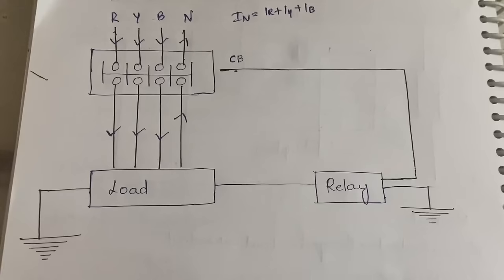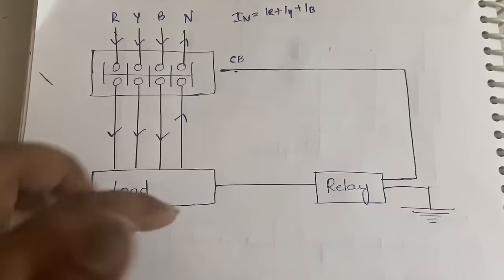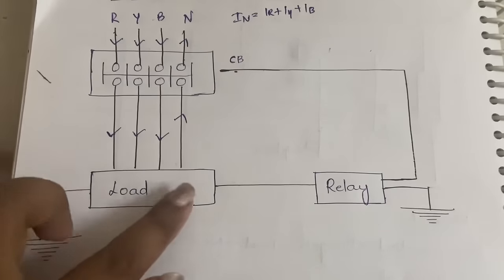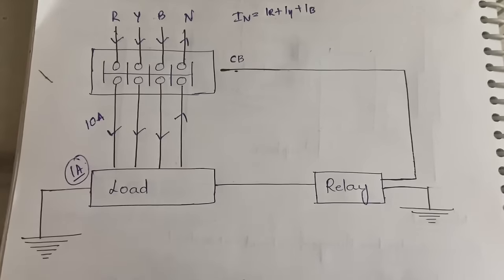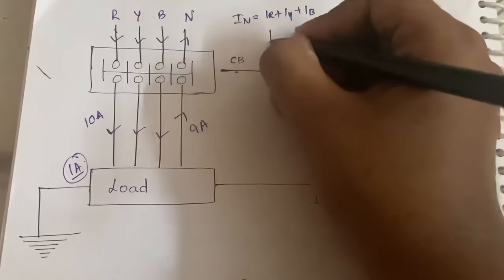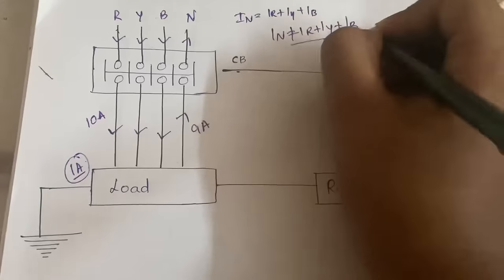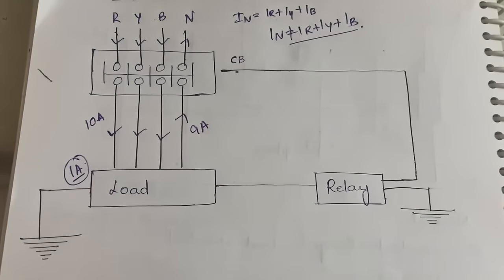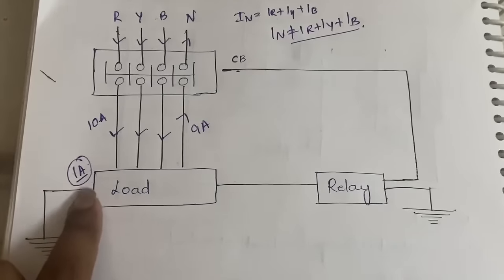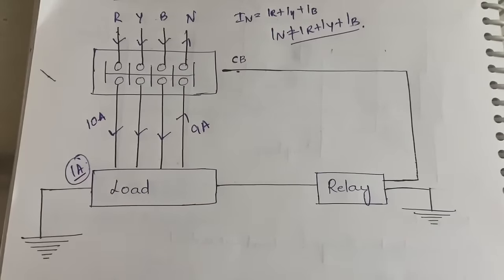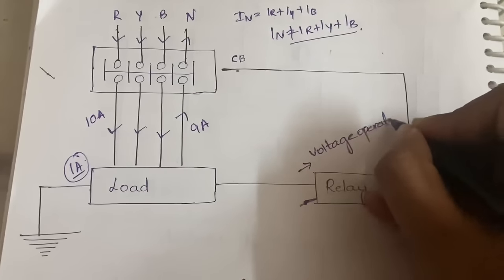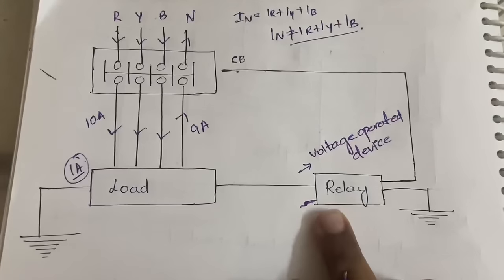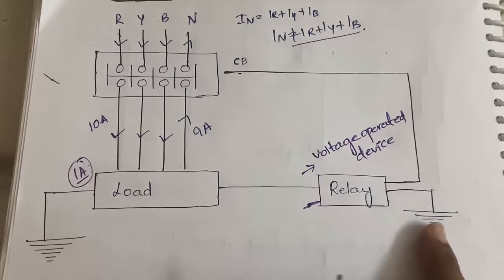But suppose current is being leaked — in that case, if we are sending 10 amperes through R, Y, B and 1 ampere is leaked, only 9 amperes is sent through neutral. So IN is not equal to IR + IY + IB. This 1 ampere of leaked current will go to the ground through the relay. The relay is a voltage operated device.